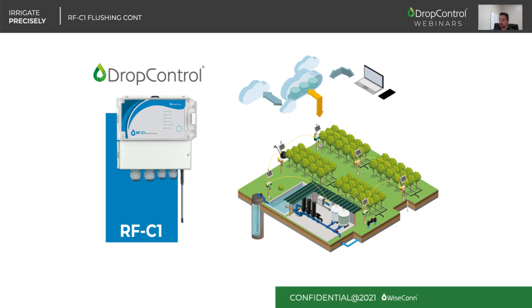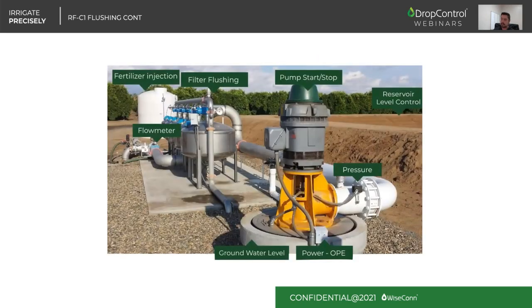So we can monitor the sensor information through our computer, tablet, or cell phone, and we can also have control over them. So our main focus lately is that we do have the C1 as the main control unit in every single filter station. That's the main purpose, the main aim whenever it got developed. And one of the reasons is that with the same control unit, we are already capable of monitoring the groundwater level in the well. You can control any pump start and stop. You can monitor the pressure downstream of the pump.